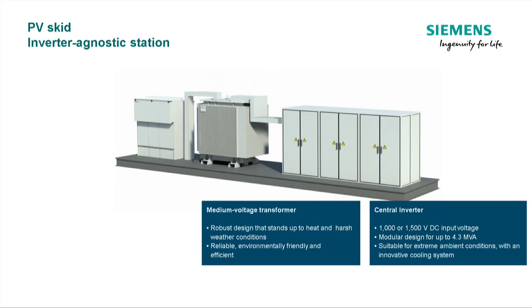So if you look at each of those three parts, as I told you: the ring main unit is for protecting your circuit in failure case - all the other inverters, if you have 100 in a field, you don't want disturbance going into the others. So therefore we are placing ring main units here. We are going for the medium voltage with our transformers.